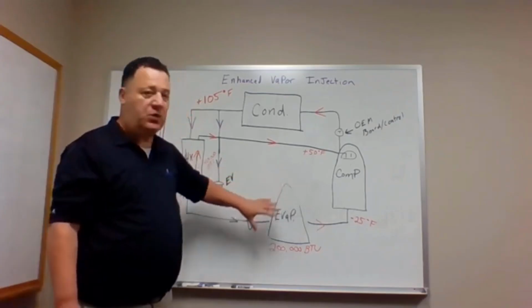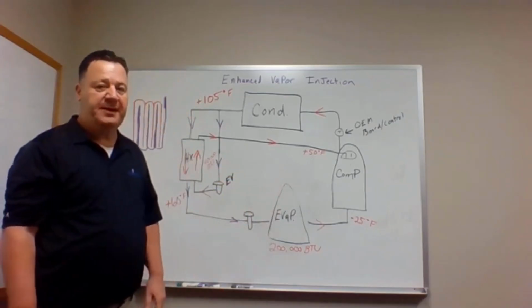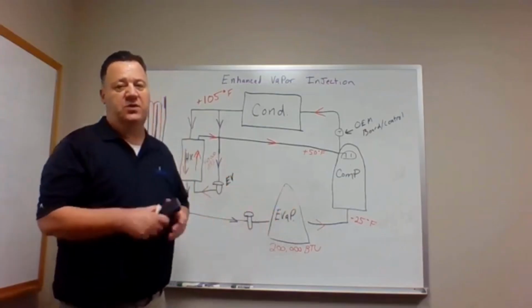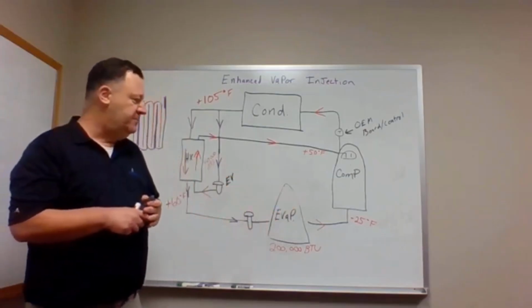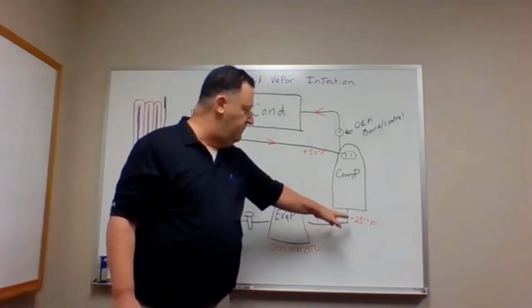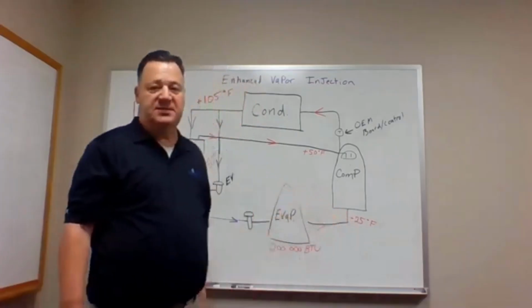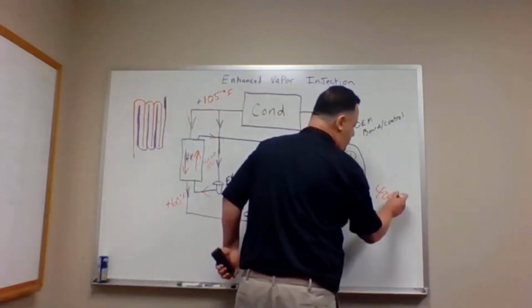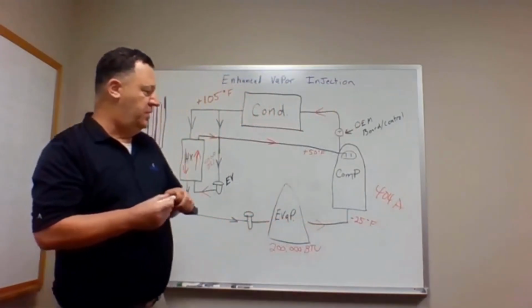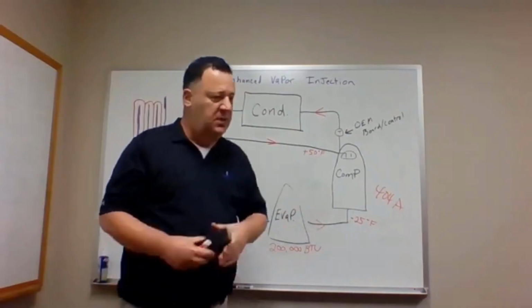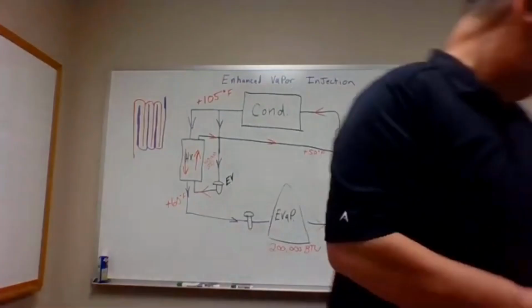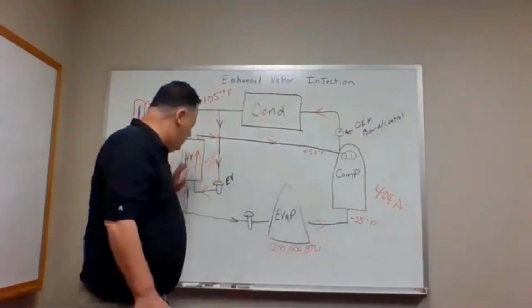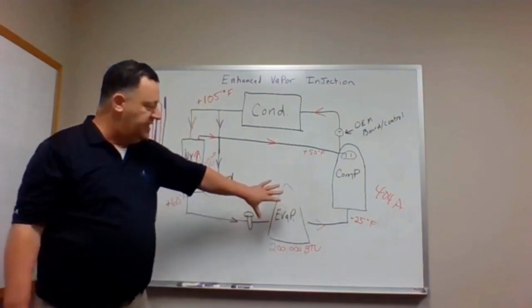which helps give us much more capacity on our evaporator, okay? This makes it much more efficient with more subcooled liquid there, all right? We typically would be going in at minus 25, let's say we're using 404A. I didn't look up the numbers, but let's say we're using 404A at minus 25. Now, at minus 25, so that's what we're gaining right there on the subcooled liquid side, the capacity on the evaporator.